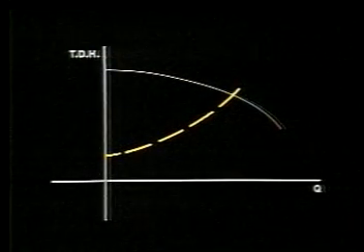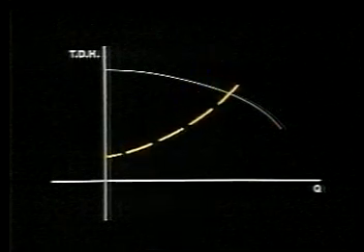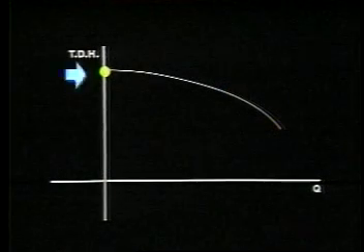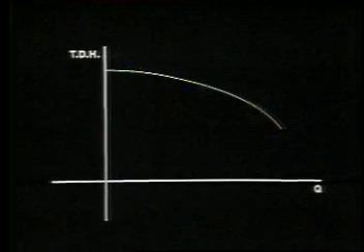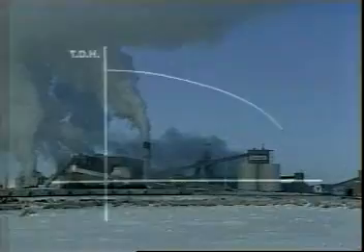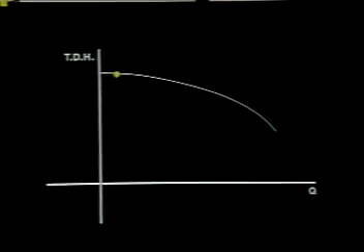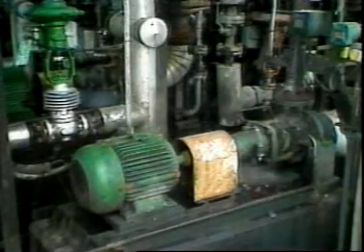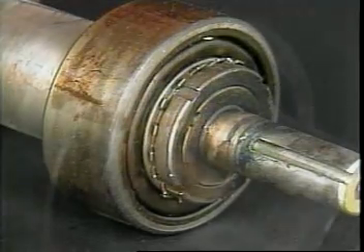The change in friction losses will cause the system curve to move, causing a movement of the operating point back or forward along the pump curve. Operating at shutoff also occurs when the pump is run against a closed discharge valve. A centrifugal pump rarely operates at one capacity but frequently moves along the curve — this is typical of normal pumping systems. Many industries try to minimize these operational fluctuations, but this is not always possible. At such times, the pump can be subjected to wide variations in system pressure, causing it to operate at very low or very high capacities within short time intervals. Centrifugal pumps are generally not capable of handling excessive continuous fluctuations on a regular basis.